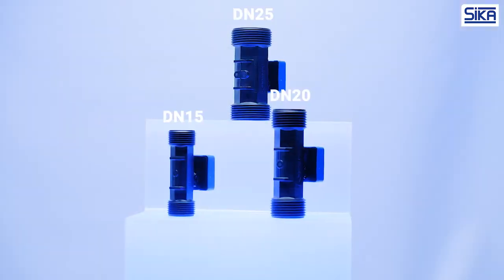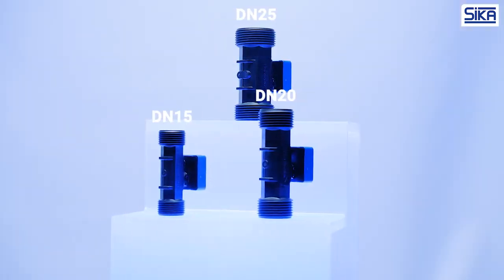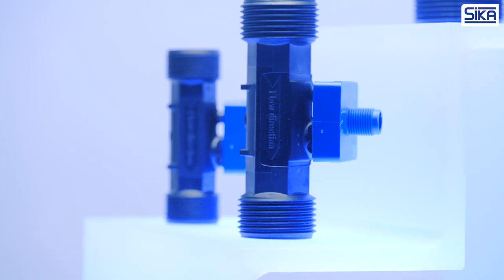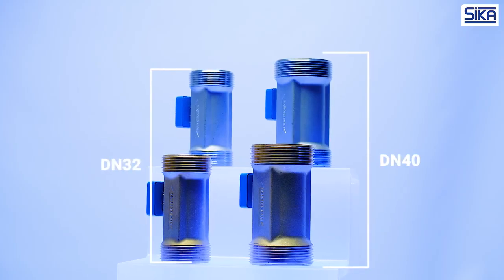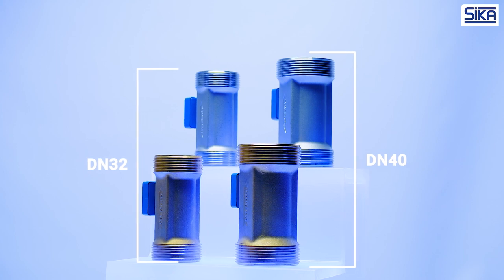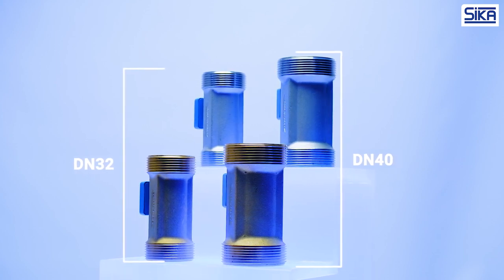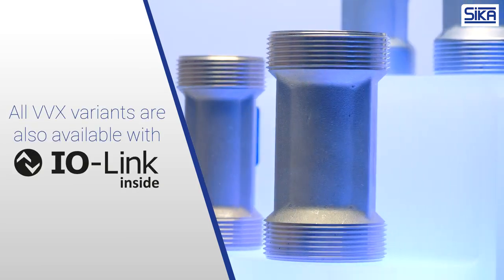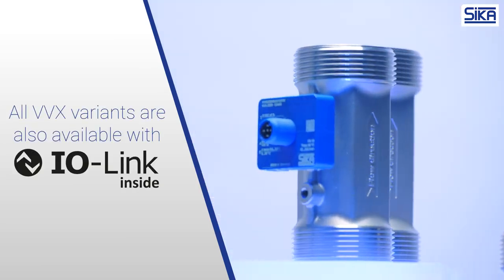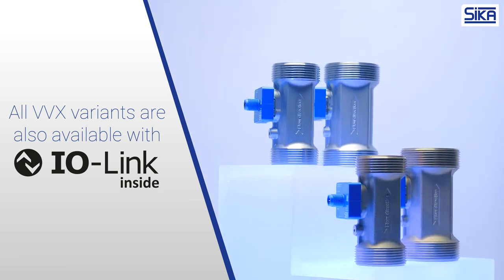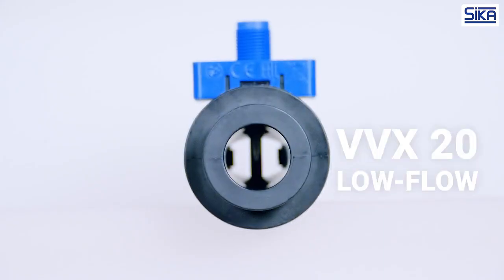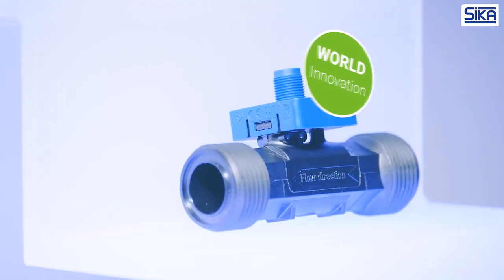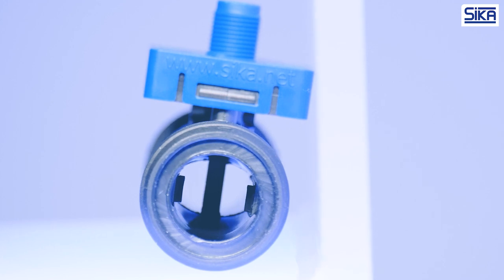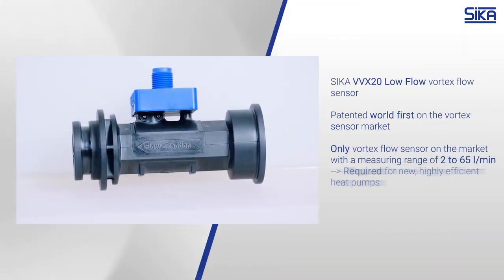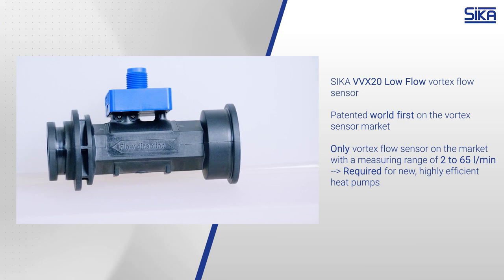The Vortex flow meters made from plastic are available in the nominal diameters of DN15, DN20, and DN25. The sensors need to be a bit more robust at larger diameters, which is why SIKA offers the nominal diameters of DN32 and DN40 in either brass or stainless steel, either with a threaded connection or the quick fasten system. For use in modern heat pumps, SIKA offers the VVX LowFlow, a world first in sensor technology. It is the only vortex flow sensor on the market that can cover the measurement range of 2 to 65 liters per minute required for modern heat pumps.